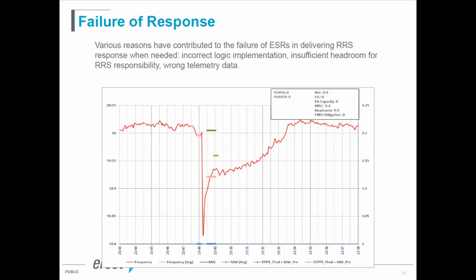We have seen from our operation experience that some of these batteries could fail to deliver this response reserve when we needed them to, because of a variety of reasons. Some of those failures were caused by incorrect logical implementation, sometimes by insufficient headroom to provide the responsibility, and sometimes due to wrong telemetered data for the state of charge.